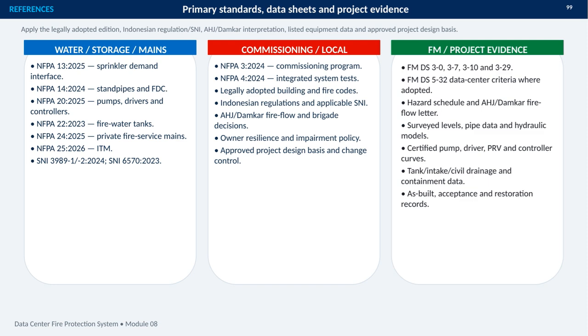The commissioning and local requirements add another layer. NFPA 3 addresses the commissioning program, while NFPA 4 addresses integrated system testing. These must be coordinated with adopted building and fire codes, fire flow decisions, owner resilience and impairment policies, and formal change control. Finally, the design should be supported by FM guidance and project evidence, including hazard schedules, surveyed levels, hydraulic models, certified equipment curves, tank and drainage information, and complete as-built, acceptance, and restoration records. Together, these references create a traceable basis for design, approval, testing, and future maintenance.